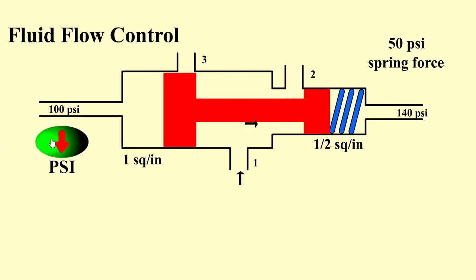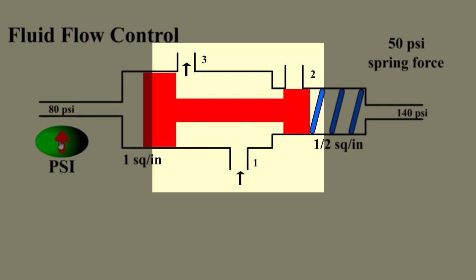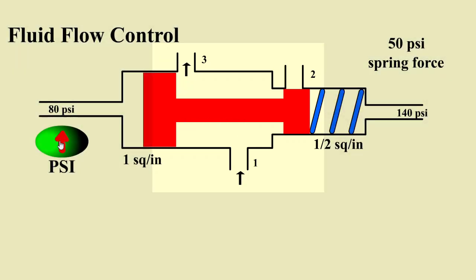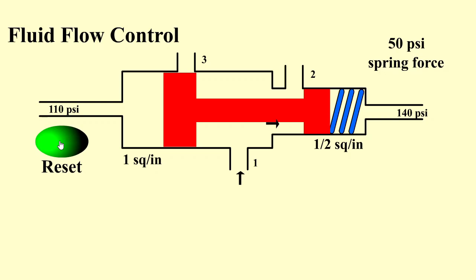If we lower the pressure on the left hand side from 100 psi down to 80 psi, the force on the right hand side pushing the valve to the left becomes dominant, closing off port 2 so fluid travels from port 1 out port 3. This is what we use to control fluid flow through a spool valve. If we raise the pressure on the left hand side back up to 110, the valve moves back and fluid is sent from port 1 to port 2, closing off port 3.